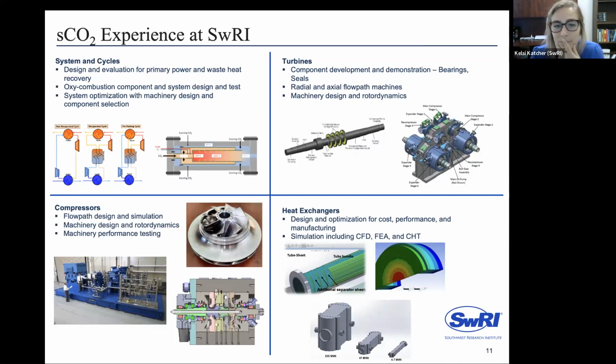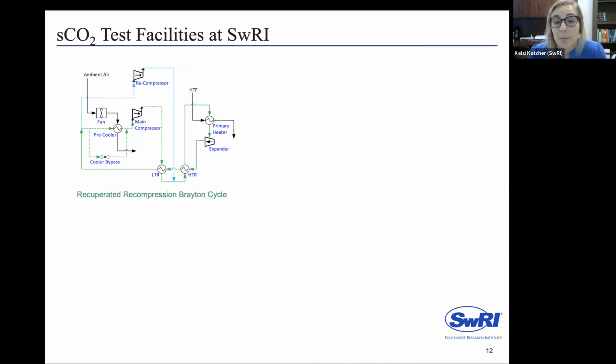A lot of our bigger test facilities are designed specifically for the recuperated recompression Brayton cycle - a supercritical CO2 cycle, but a much higher temperature cycle. Coming into your expander, we're at maybe 260 bar and 700°C. This is looking at utility-scale power generation, where you might have a fired cycle, or use concentrated solar or nuclear, something with very high temperatures allowing much higher cycle efficiencies. Here are some of the facilities we've built around this.